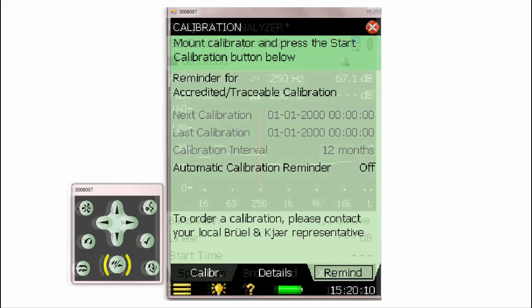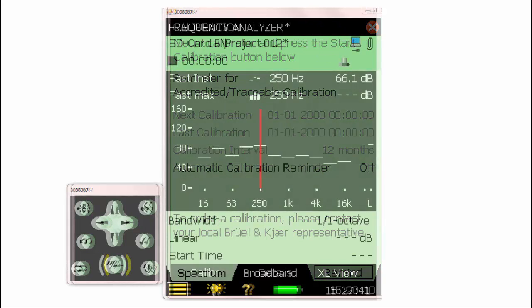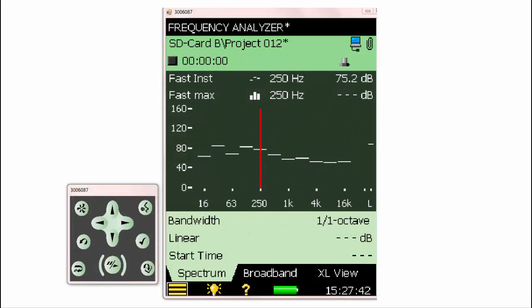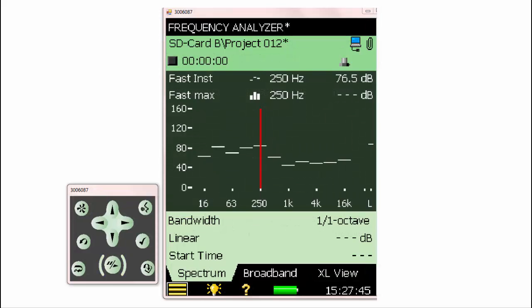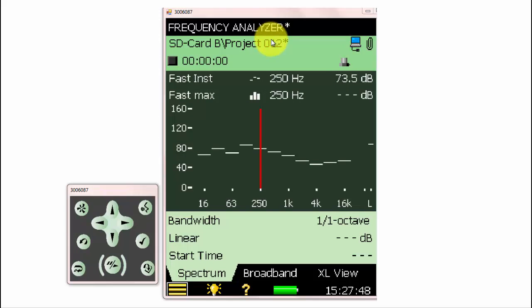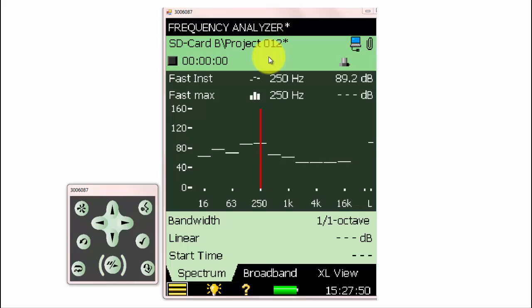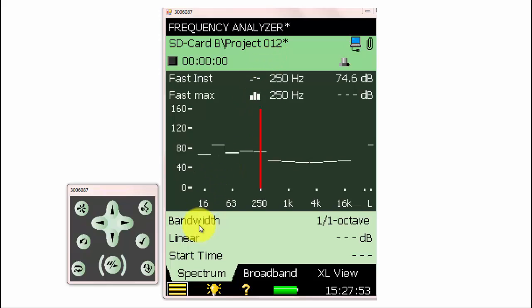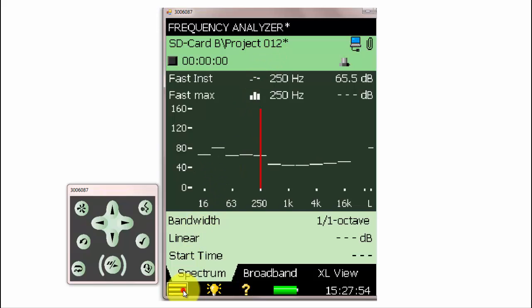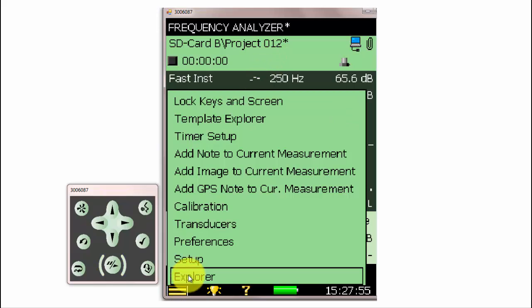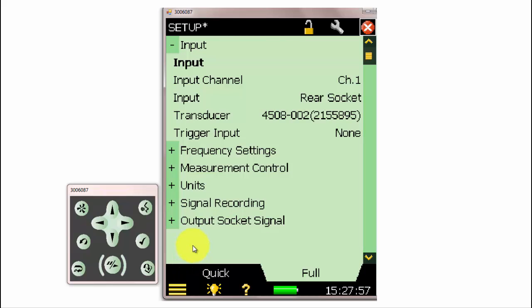Next, let's take a look at how to calibrate an accelerometer on the 2250 or 2270. First, we'll want to make sure that the accelerometer is properly selected under Setup. Our accelerometer will be plugged into the rear socket, and I have the transducer selected by its serial number.